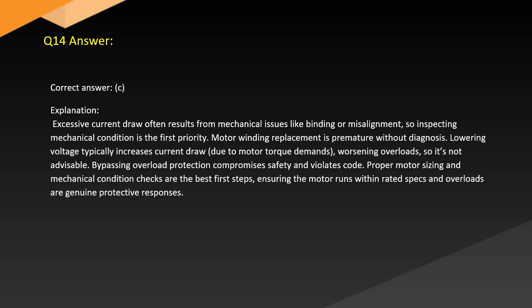Answer. Correct answer. C. Explanation. Excessive current draw often results from mechanical issues like binding or misalignment, so inspecting mechanical condition is the first priority. Motor winding replacement is premature without diagnosis. Lowering voltage typically increases current draw due to motor torque demands, worsening overloads, so it's not advisable. Bypassing overload protection compromises safety and violates code. Proper motor sizing and mechanical condition checks are the best first steps, ensuring the motor runs within rated specs and overloads are genuine protective responses.